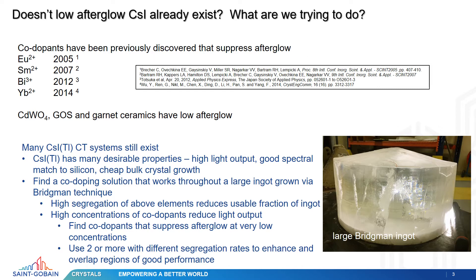The elements listed previously — europium, samarium, bismuth, ytterbium — have high segregation coefficients, which can reduce the portion of the ingot with suitably low afterglow and suitably high light output. When they segregate, we get low concentrations of the co-dopants at the top of the crystal and high concentrations at the bottom, yielding regions of poor afterglow suppression at the top and poor light output at the bottom. So we are looking for co-dopants that suppress afterglow at very low concentrations, and perhaps two or more in combination with different segregation rates to overlap regions of good performance.